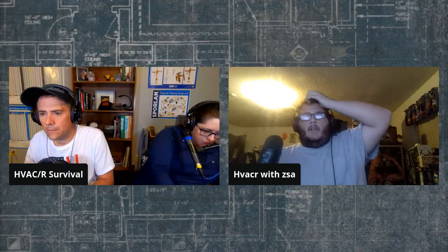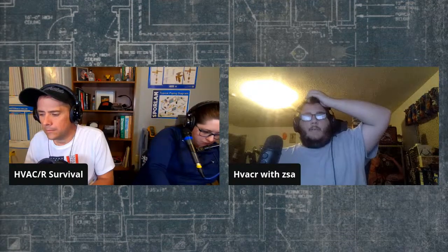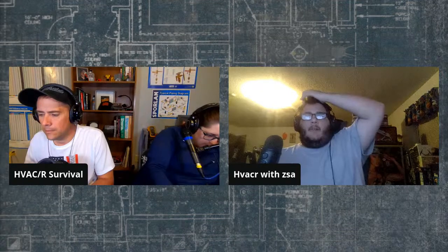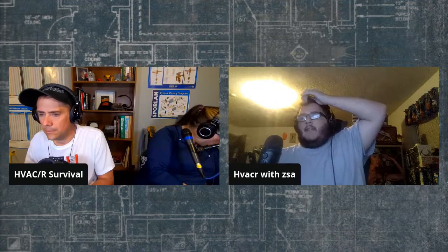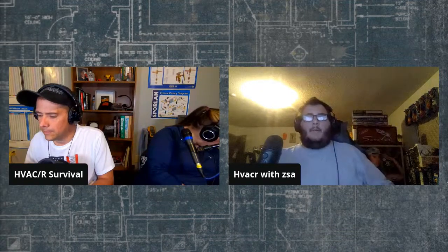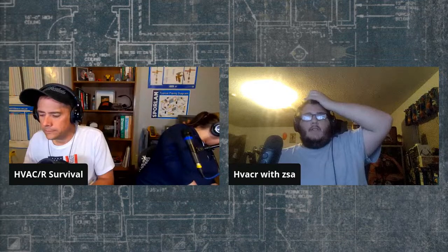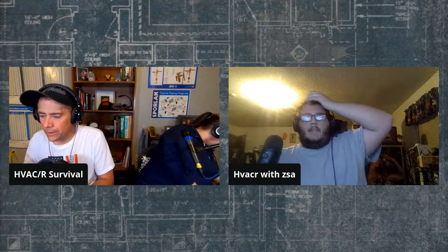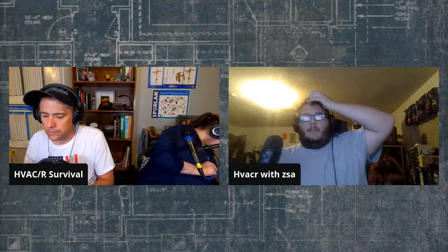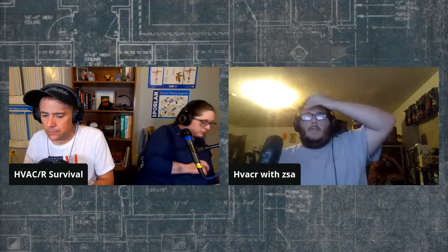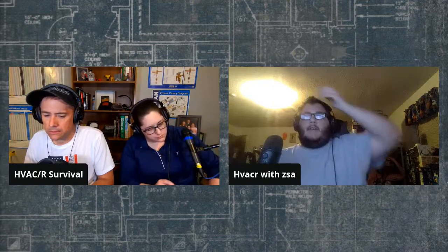Come to find out, the second evaporator was still running, believe it or not, with the breaker. When we thought he killed the right breaker, this whole time the thing was icing up even worse. What we found was that the pressure switch was stuck on both of them, not cutting them off. This is a pump down system that we set up on this gas station, and what was happening was it was going straight into a vacuum, pretty much right into a vacuum.